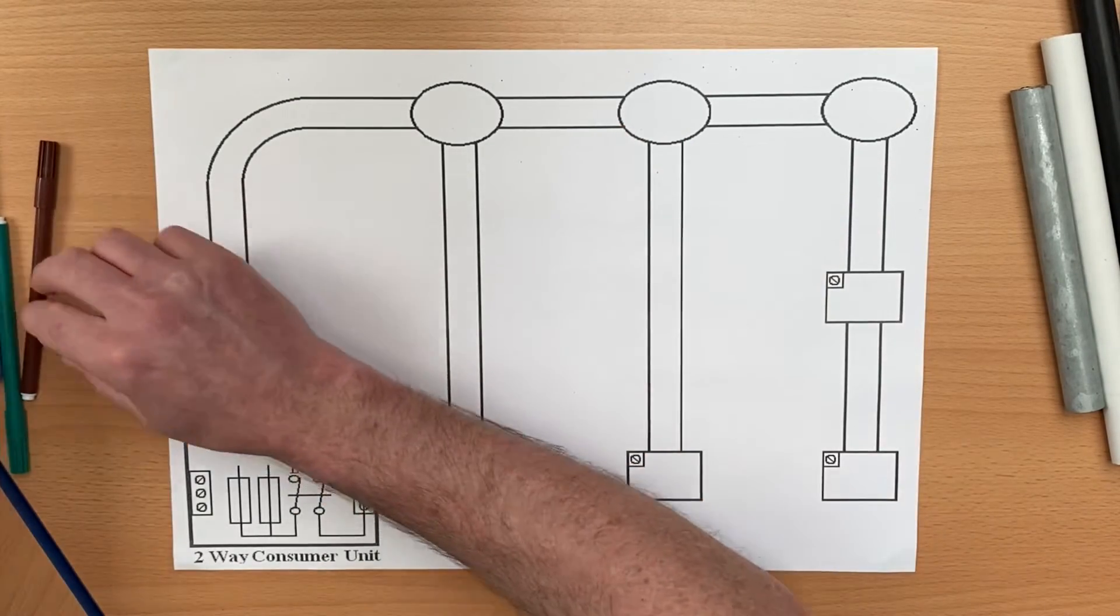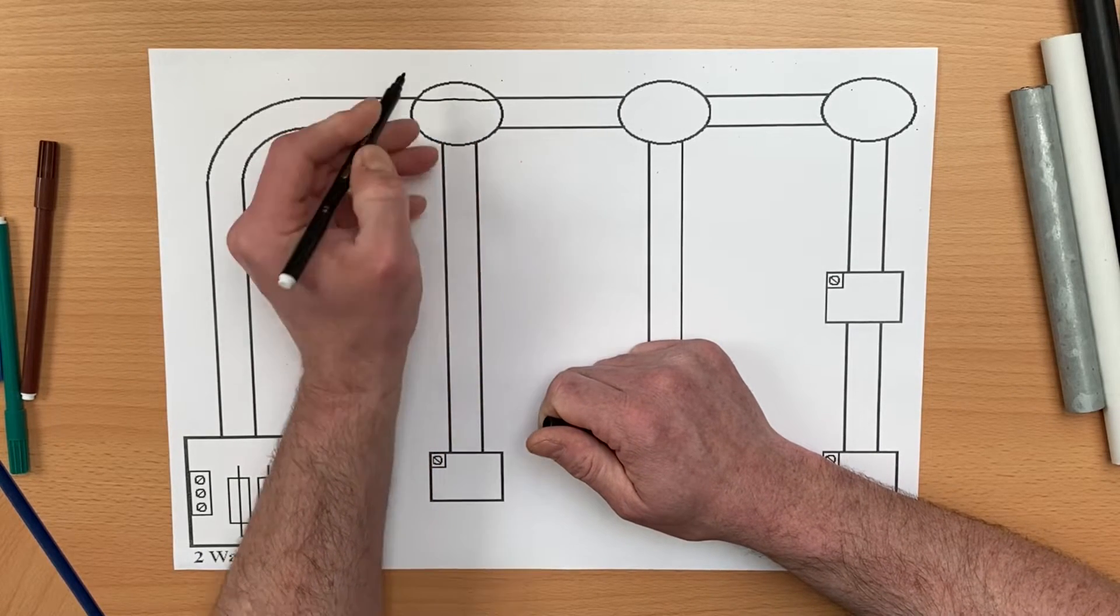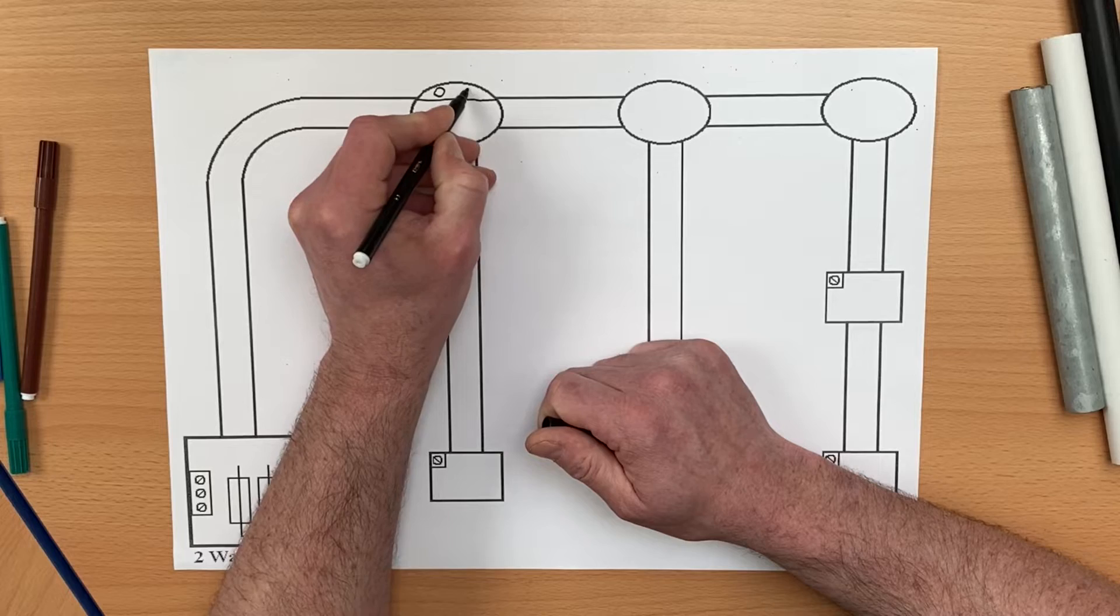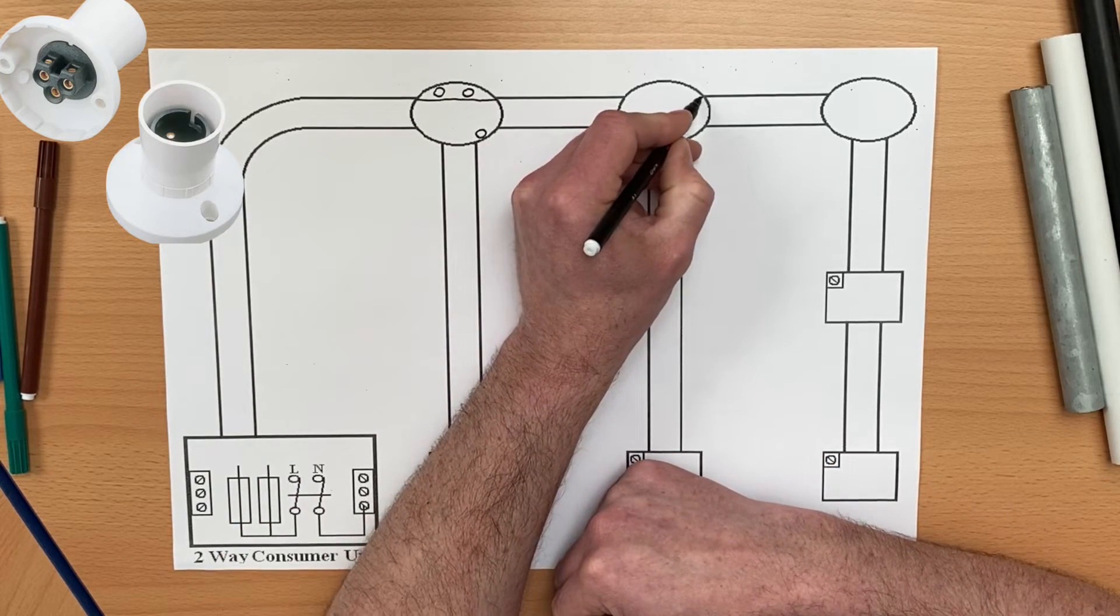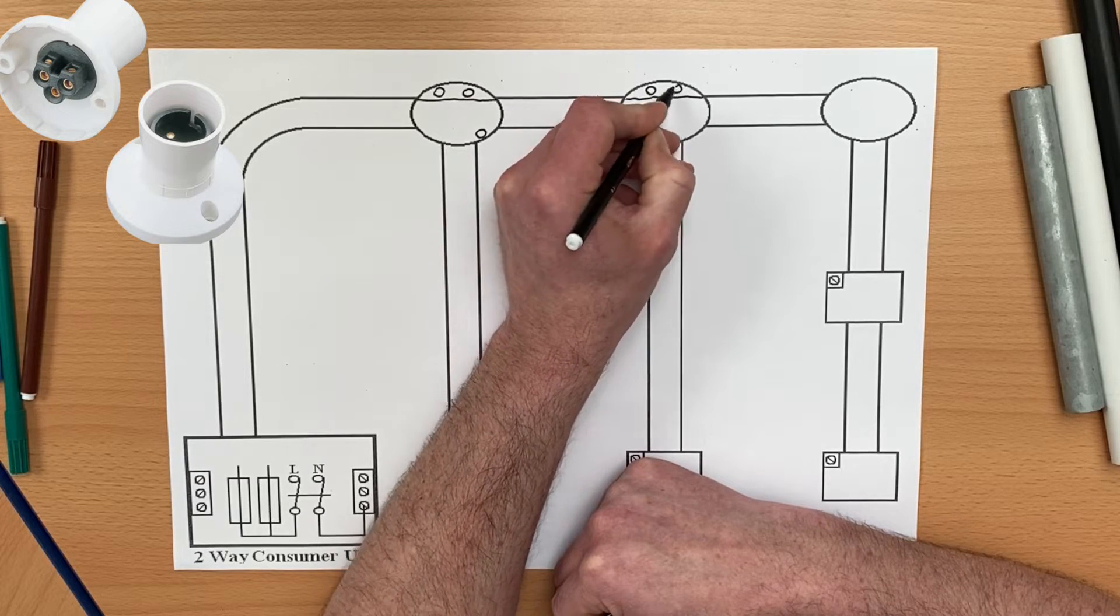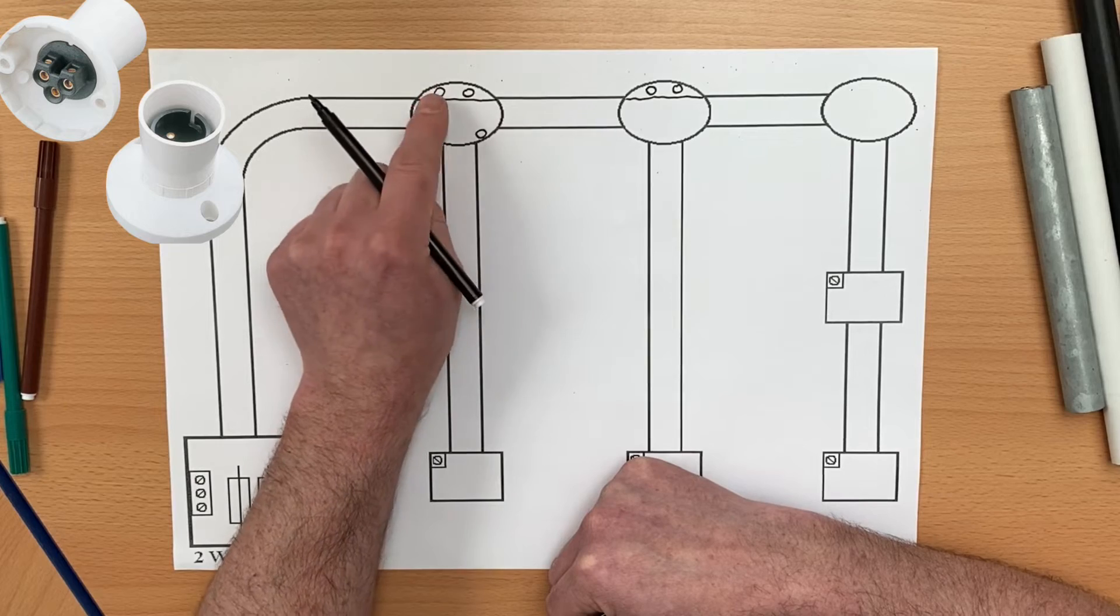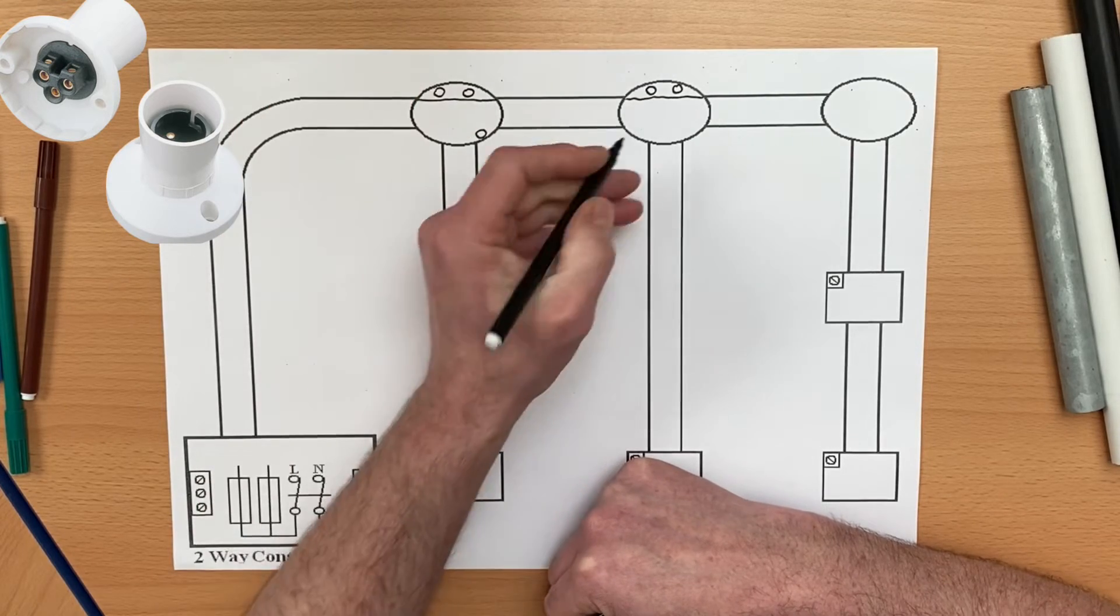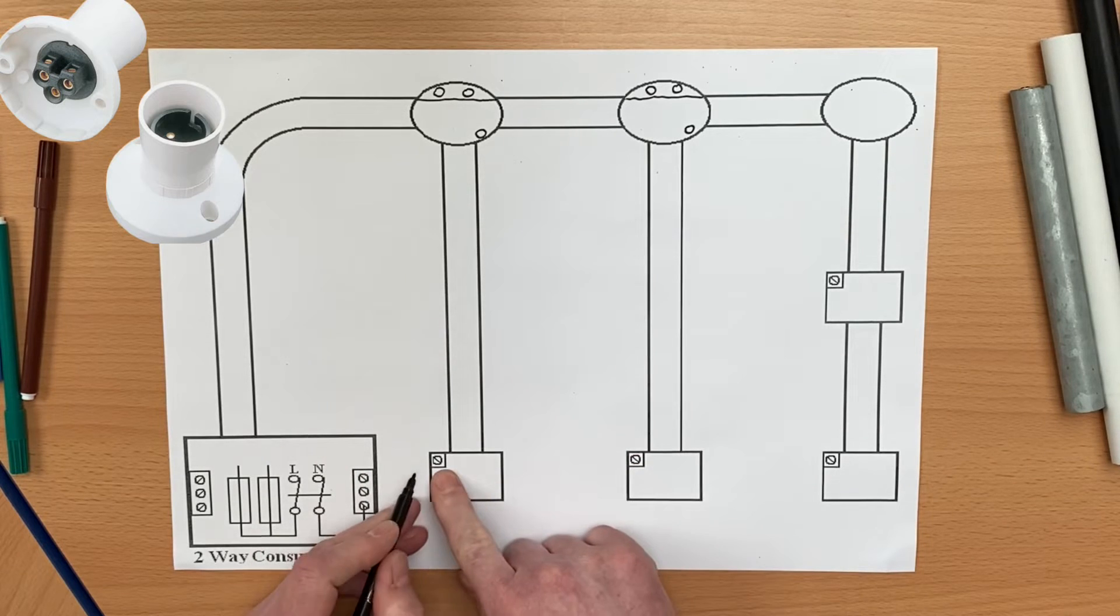I'm going to need to alter my drawing slightly to add some bits in. Remember we did this in the first one. I'm going to need to make a couple of connections here for switching line and neutral of our batten lamp holder and a CPC connection at both lighting points. It won't matter which way around our line and neutral go as long as we've got a bayonet cap lamp holder.